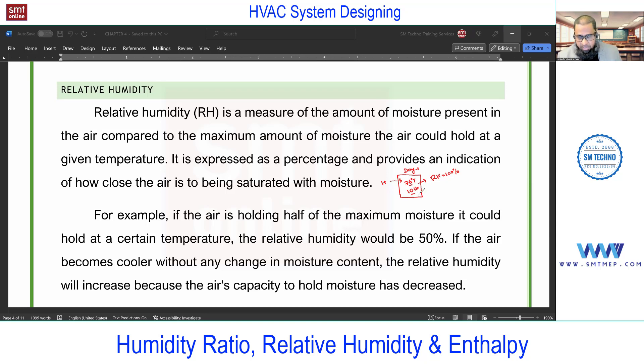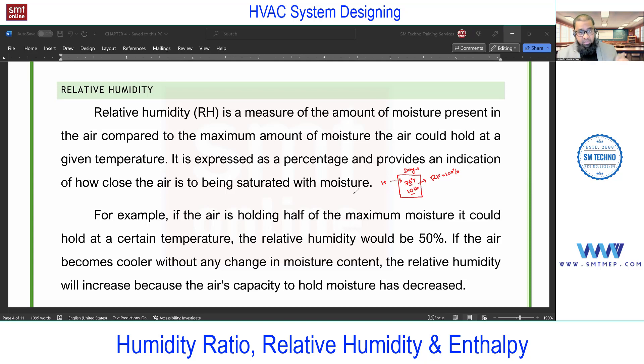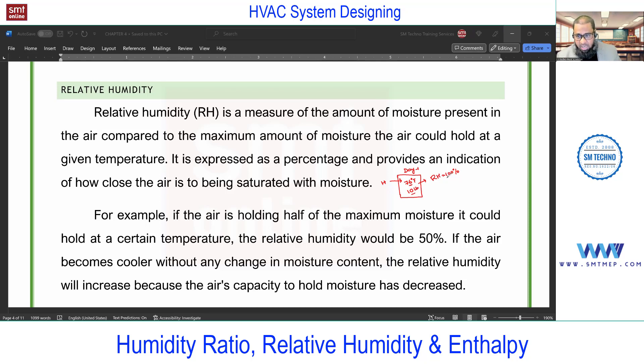When RH is 100%, we say the air is saturated — meaning it contains the maximum possible moisture content at that dry-bulb temperature. Remember, we cannot change the temperature during comparison, because as temperature increases, the moisture-holding capacity of air increases, and as temperature decreases, it decreases. So at 76°F, the maximum possible moisture is 10 pounds, meaning RH = 100%.